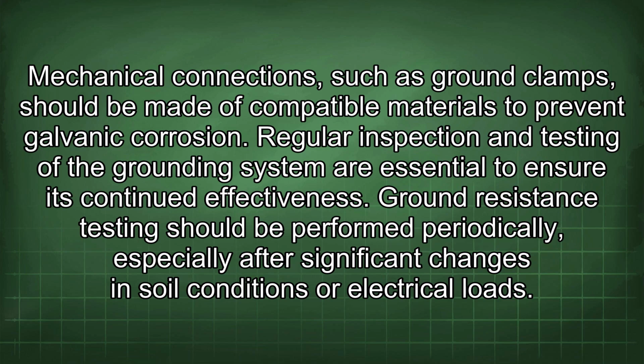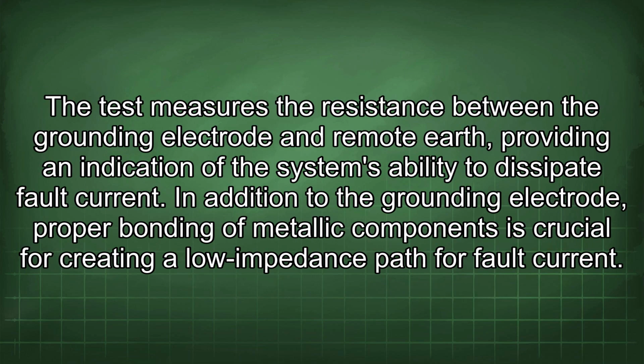Regular inspection and testing of the grounding system are essential to ensure its continued effectiveness. Ground resistance testing should be performed periodically, especially after significant changes in soil conditions or electrical loads. The test measures the resistance between the grounding electrode and remote earth, providing an indication of the system's ability to dissipate fault current. In addition to the grounding electrode, proper bonding of metallic components is crucial for creating a low impedance path for fault current.